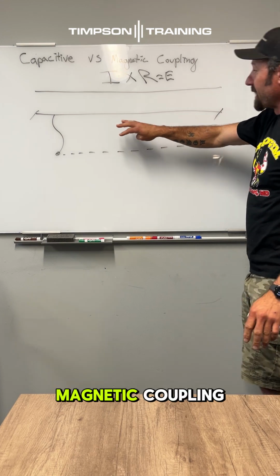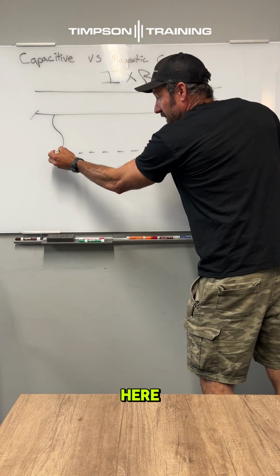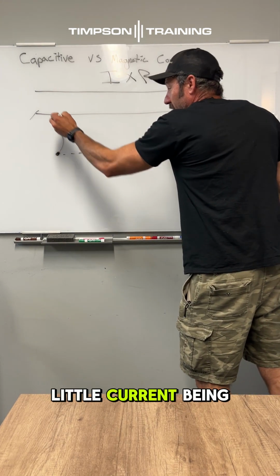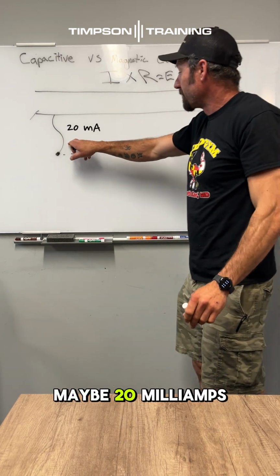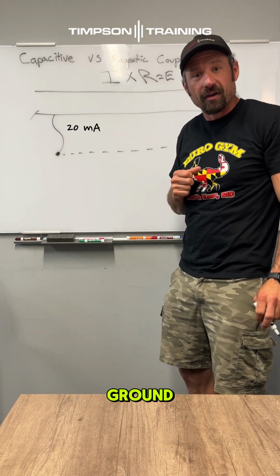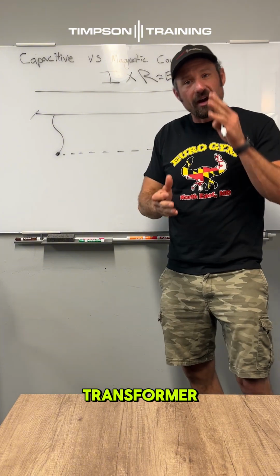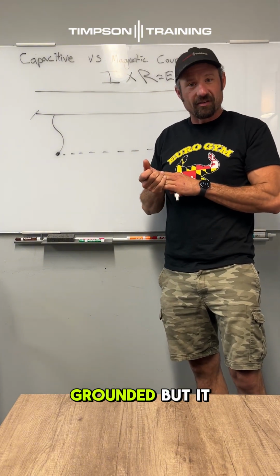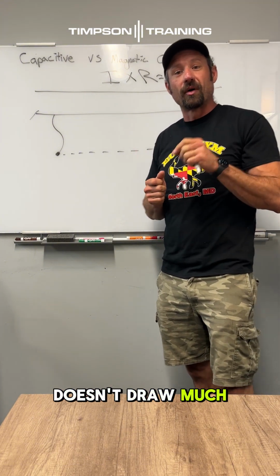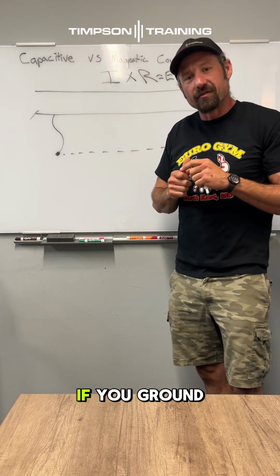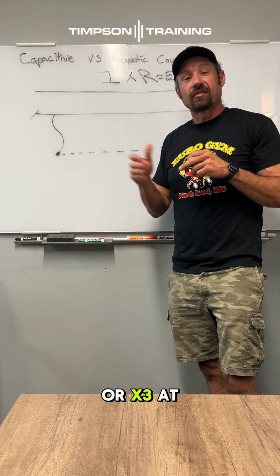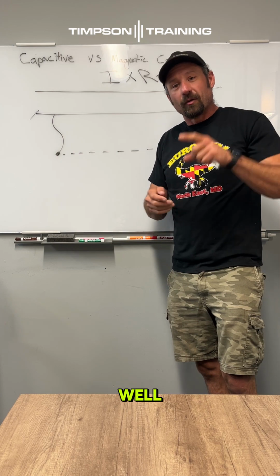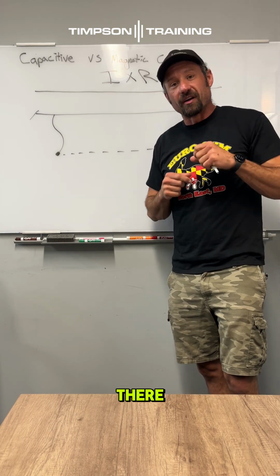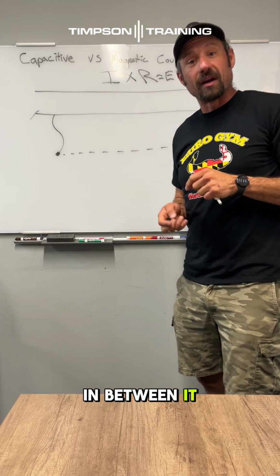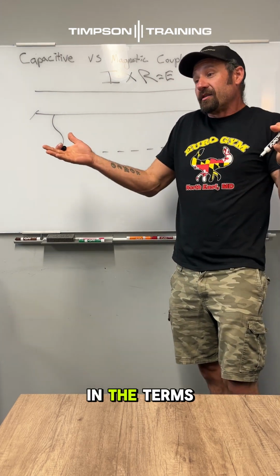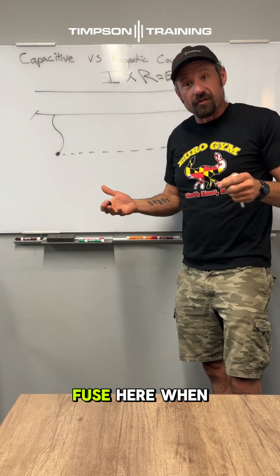So when we have magnetic coupling, you have very little current being drawn, maybe 20 milliamps from that one ground. Just like if we imagine a transformer, the X2 gets grounded, but it doesn't draw much current. But what happens if you ground the X1 or X3 at the same time? Well, you have an open circuit voltage there. And if you put a ground in between it, you draw a lot of current. In terms of a transformer, you blow a fuse.